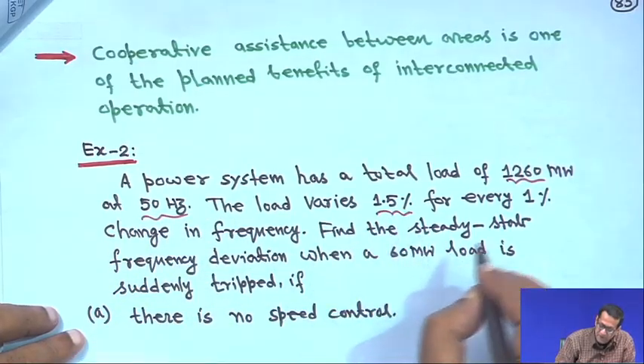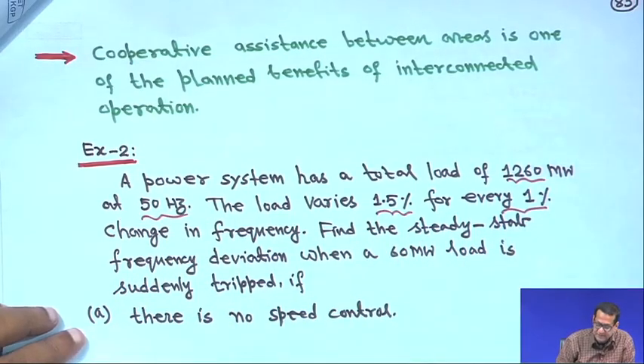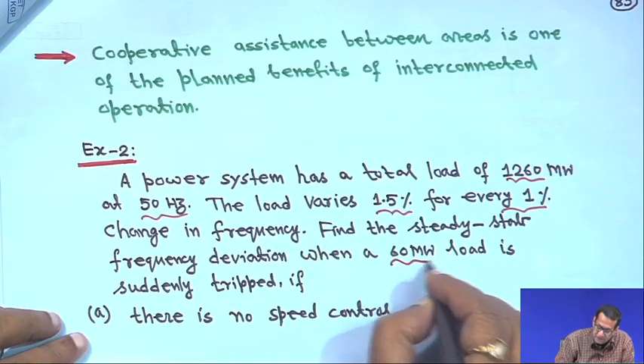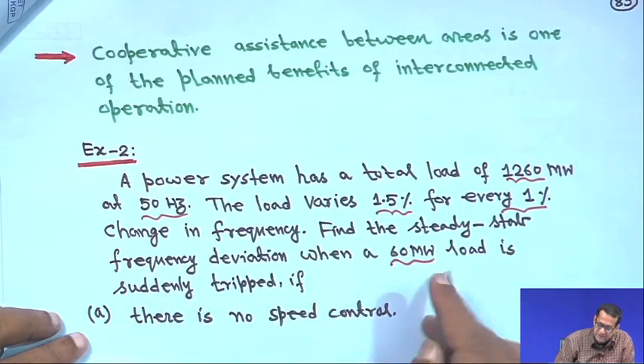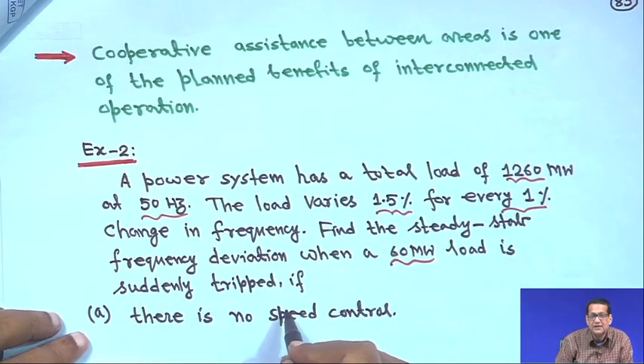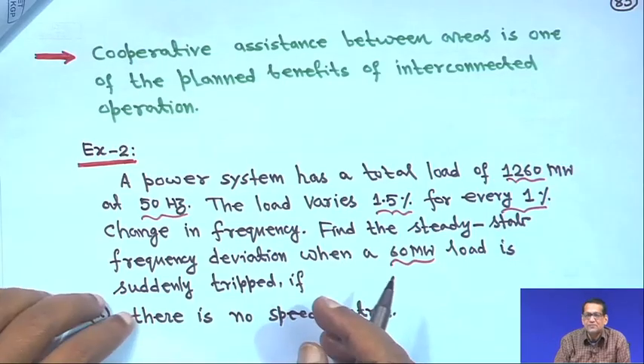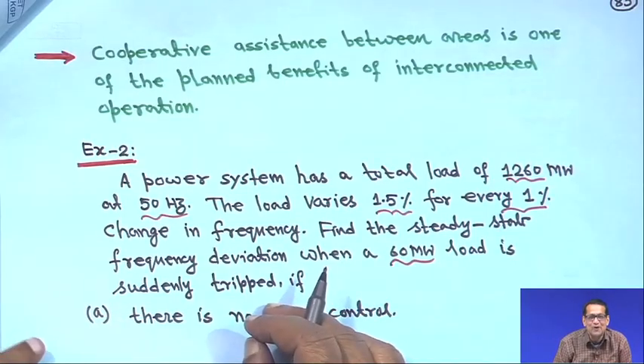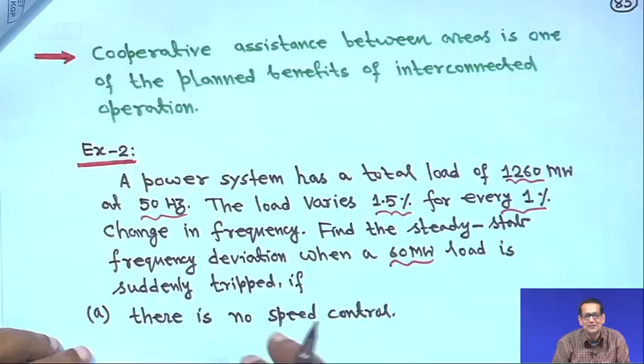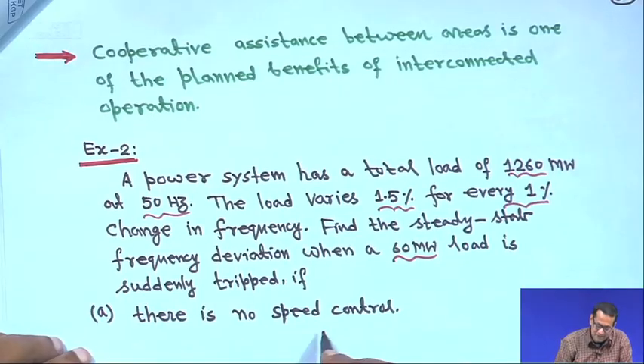Load varies 1.5% for every 1% change in frequency, and we need to find the steady state frequency deviation when a 60 megawatt load is suddenly tripped. Tripped means that load has switched off, so the load is isolated. That means the load decreases. First, there is no speed control.